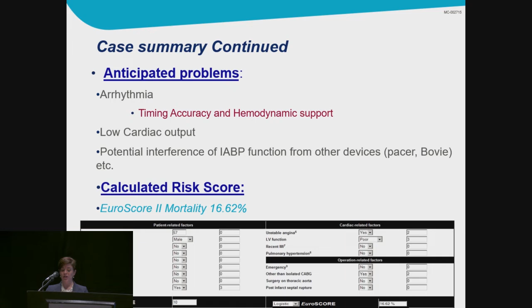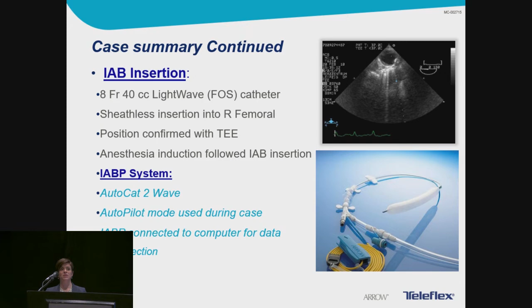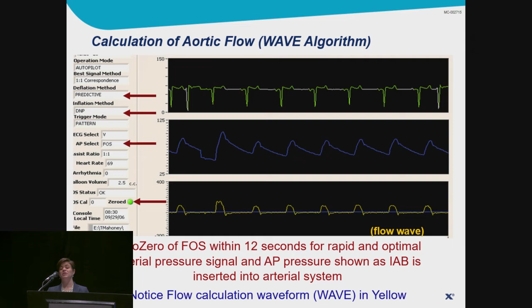Now, the catheter that we did use was a 40 cc fiber optic catheter from Arrow. It was a sheathless insertion to the right femoral, and position was confirmed via TEE. The balloon pump system used was the AutoCAT 2 Wave. We did use autopilot during the case, and all data was collected via an external PC connected to our pump. Here you can see the third waveform is our flow wave, and that's calculated from our WAVE algorithm. What you can see is that an auto zero occurred 12 seconds after connection to the pump. With the Arrow systems and our fiber optic catheters, it is a true atmospheric zero prior to insertion, so there's no calibration done to replace that zero.